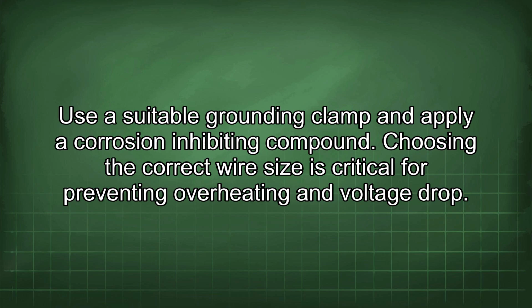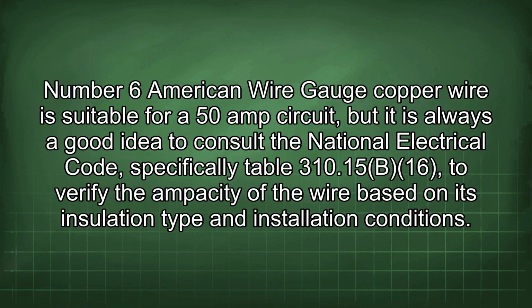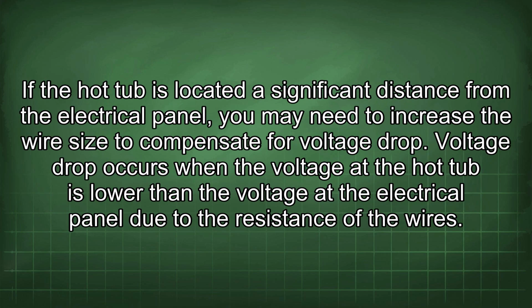Choosing the correct wire size is critical for preventing overheating and voltage drop. Number 6 American wire gauge copper wire is suitable for a 50 amp circuit, but it is always a good idea to consult the National Electrical Code, specifically Table 310.15(B)(16), to verify the ampacity of the wire based on its insulation type and installation conditions. If the hot tub is located a significant distance from the electrical panel, you may need to increase the wire size to compensate for voltage drop.